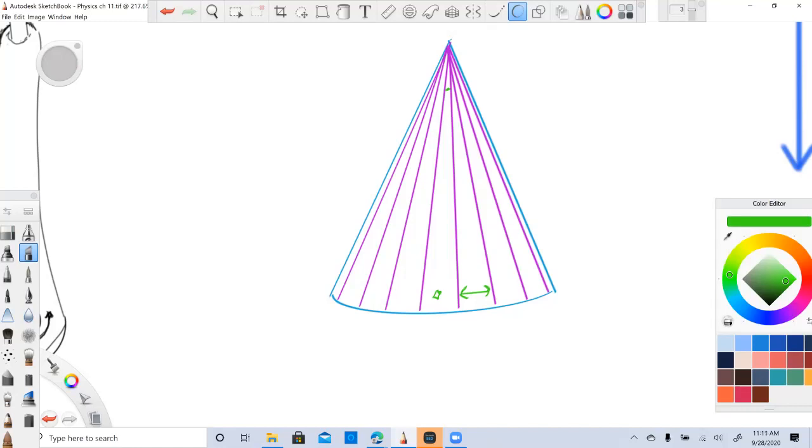With greater depth, gaps of ever-increasing size exist between the scan lines. There are computer algorithms that kind of help with this, but still it is a problem. Beam steering. So we always have to talk about how the beam is steered, if it's steered at all. Two-dimensional image is built up by rotating the crystal with the motor. Sound beams are emitted as the crystal moves, hence the scan plane is created through mechanical steering.